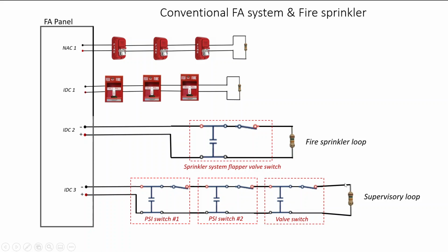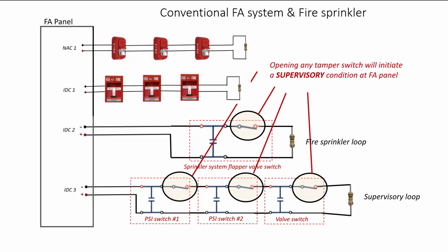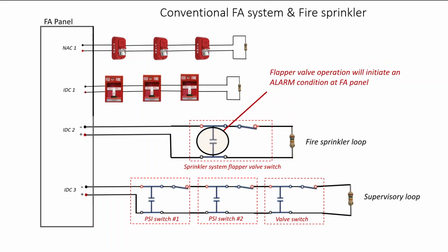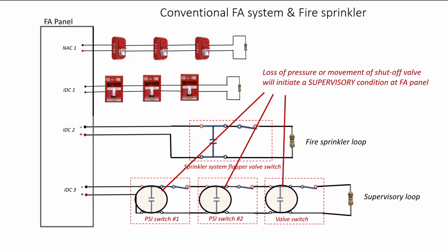Now we'll notice that each of these are then wired out to their own independent IDC loop, and this one, its own independent IDC loop. The manufacturer will indicate which IDC loop I should terminate things onto in order for it to distinguish between a flapper valve, which would send it into alarm, and a supervisory device, which would send it into supervisory. So, to confirm, opening any tamper switch will initiate a supervisory condition at a fire alarm panel. The flapper valve operation should initiate an alarm condition at the fire alarm panel. And loss of pressure or movement of the shutoff valve should initiate a supervisory condition at the fire alarm panel.